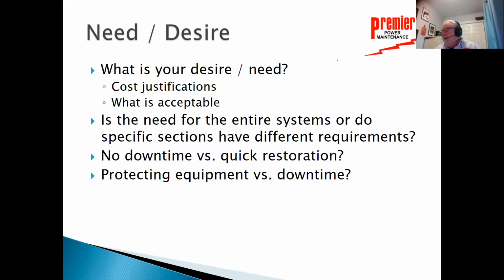So let's look at needs and need assessments. When we look at what we desire and what we need, those are two totally separate things. So we can have cost justifications for all those things that we need. What truly is acceptable for us in the operation of our electrical system? Is there truly a need for the entire system to be a certain reliability, or can we have different requirements for different sections? Are we looking at the situation where no downtime is acceptable versus quick restoration? Now, I go back to my old utility days. We wanted a reliable, robust transmission and sub-transmission system, but when it got down to the distribution, we were in the mode for quick restoration because we didn't want to spend all the time maintaining all the parts of the distribution system.